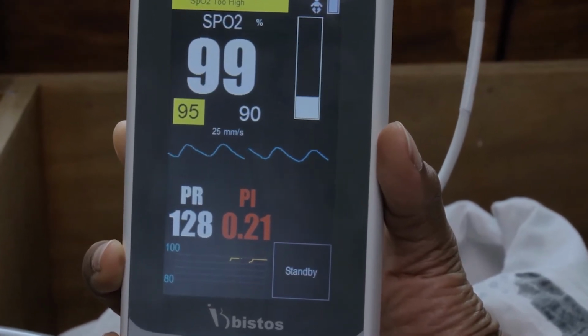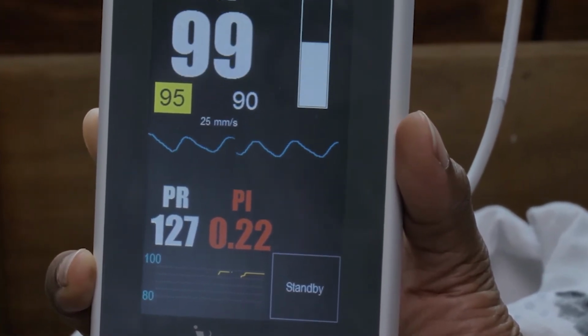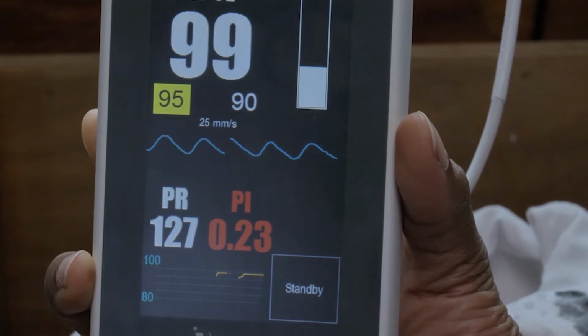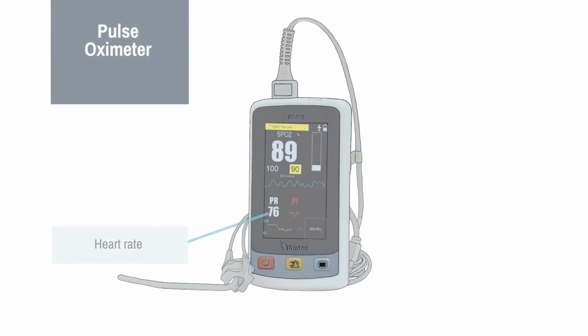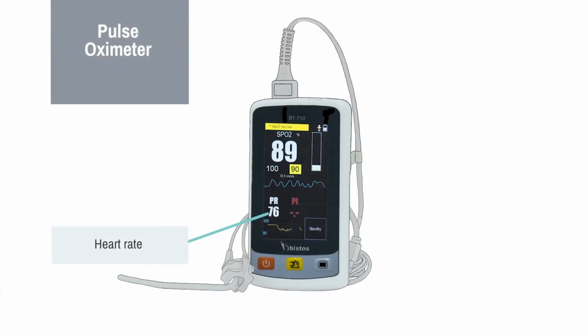If you have a good waveform, it means that the machine is reading the baby's pulse accurately, in which case the other readings should also be accurate. The pulse or heart rate will appear below the waveform. If you do not have a good waveform, it is the wrong shape or not there, then the machine is not getting enough information from the probe and it can give false readings.